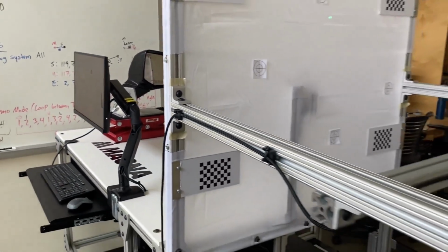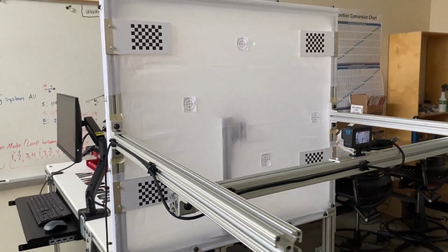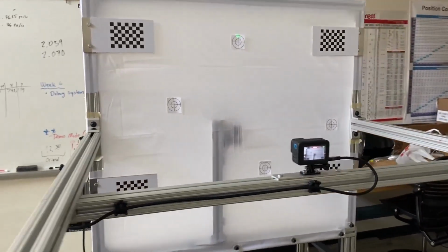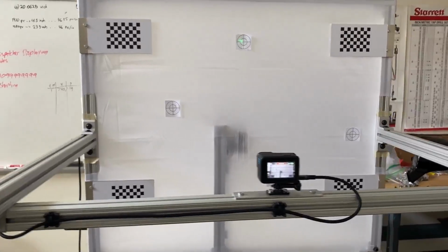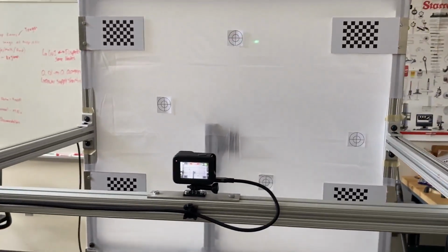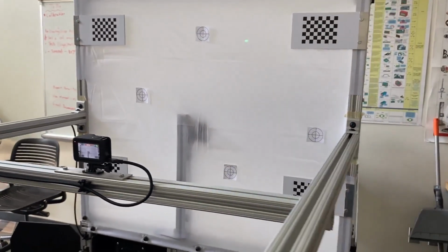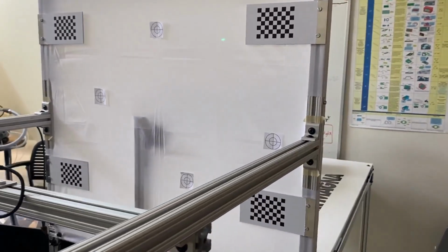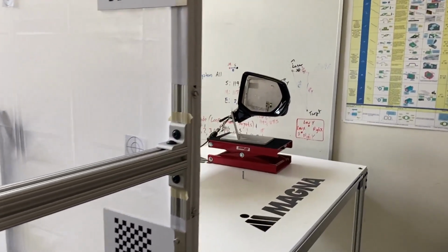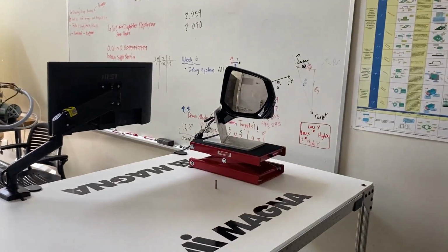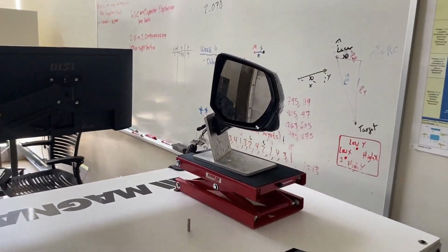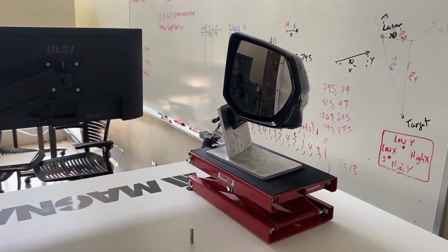The manual test allows the user to move to a number of desired targets manually, up to 5 targets. Once all targets are reached, the system will automatically go back to each target and collect the position of the actuator and the angle difference between the set and recall values. The 4 spec test follows this specification, reaching a total of 17 target locations automatically.